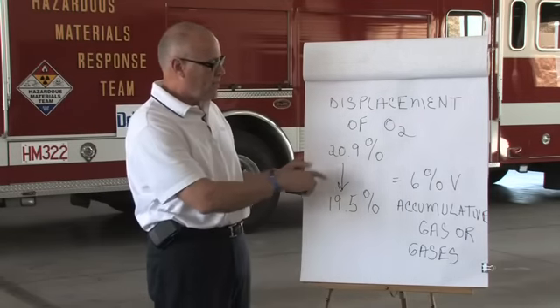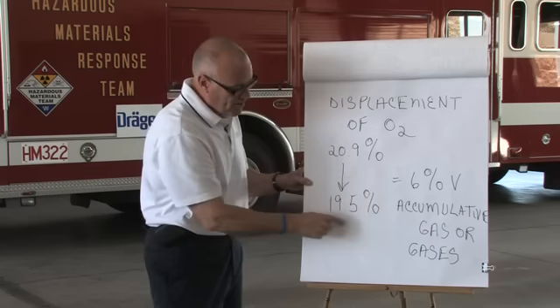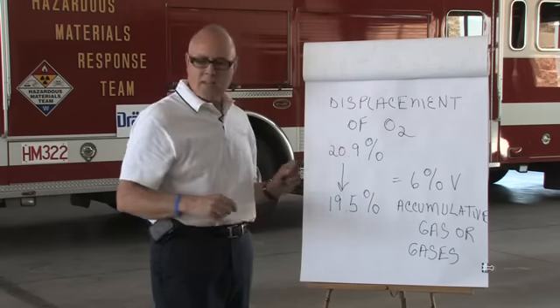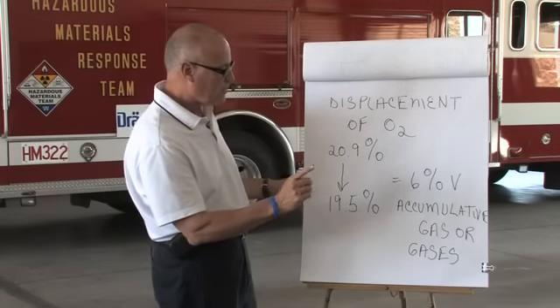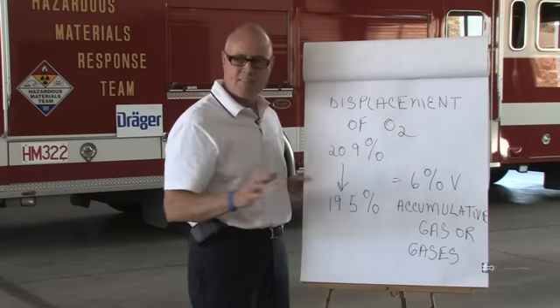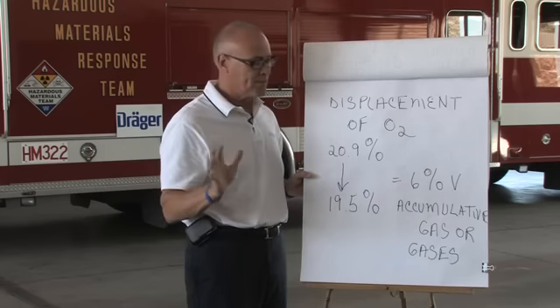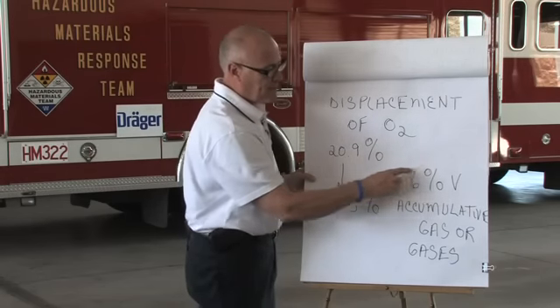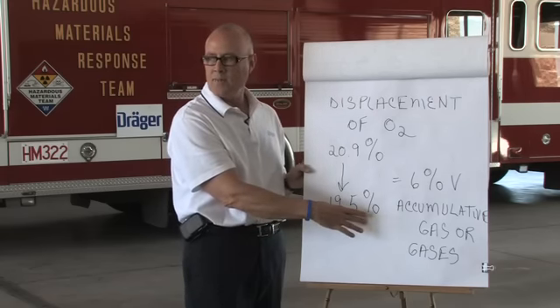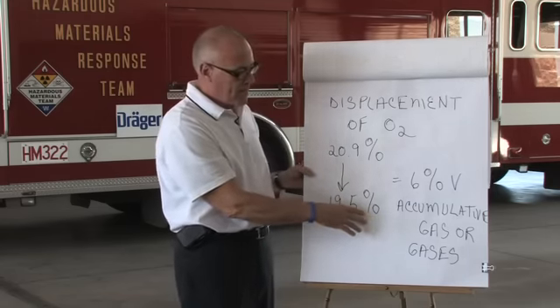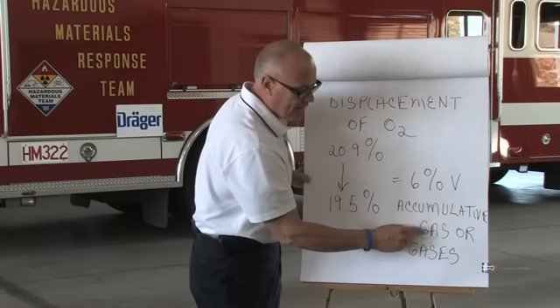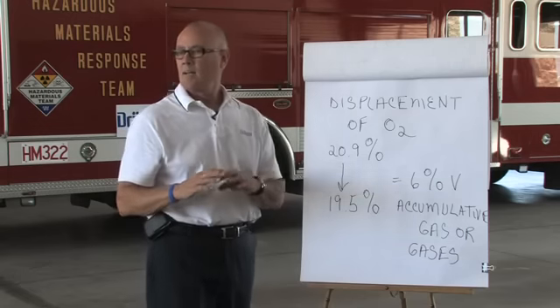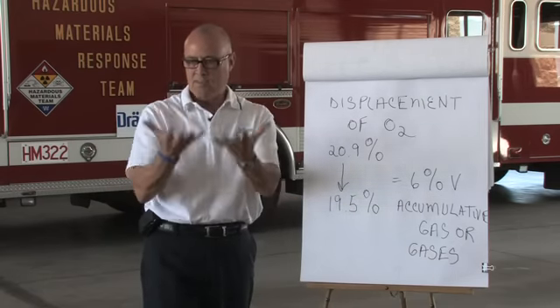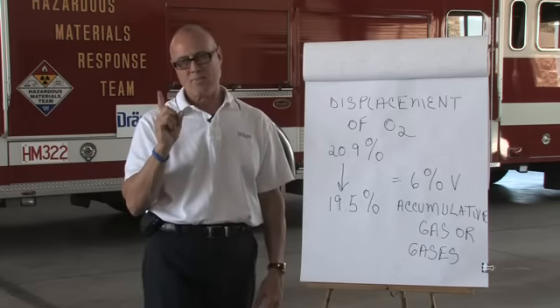But generally what happens to drive your oxygen from 20.9 down to your alarm point of 19.5, another gas has got to be there to displace that oxygen. The bottom line is this. It takes roughly 6% by volume, and this is not an exact figure, all right? So that's important you realize that. In the neighborhood of 6% by volume will drop your 20.9 O2 down to your A1 alarm, which is your latching alarm on your Draeger instruments. Okay? And this could be, that's why I said a cumulative gas or gases. It could be a number of gases that have accumulated together to drive your oxygen down. But in most cases, it's usually just one.